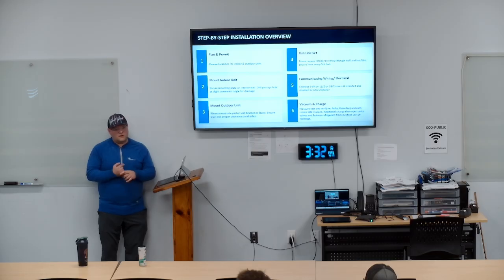Support for you guys, we need to support the line set every 5 feet. We do 6 feet and then there's a sag right in the middle. Unless you have shields. If you have shields, you can go 6 foot on centers because the shields extend 6 inches past the clamps.